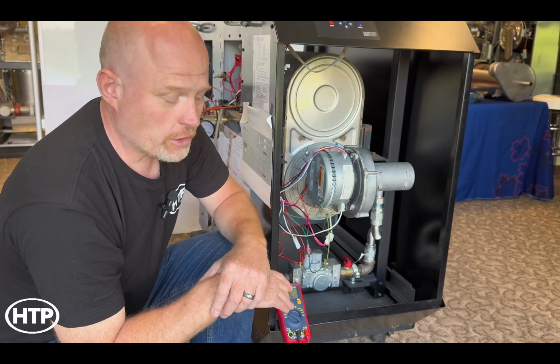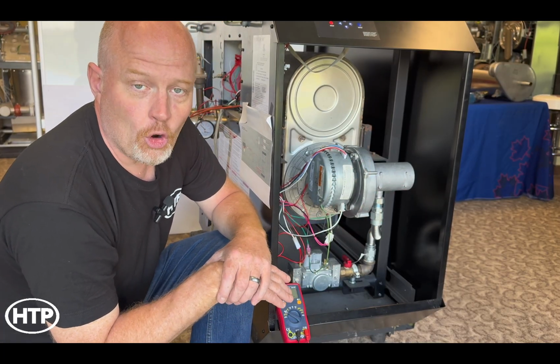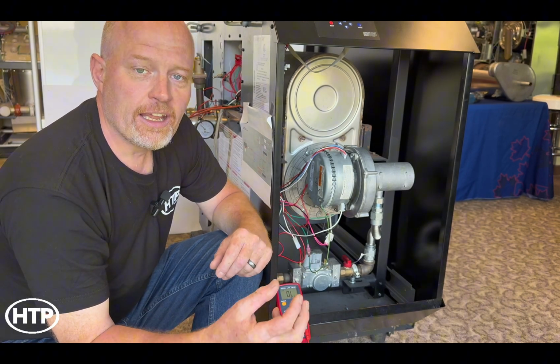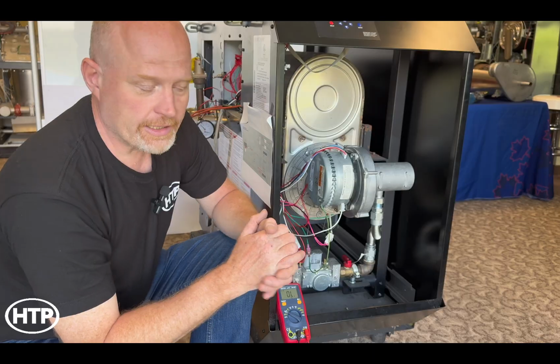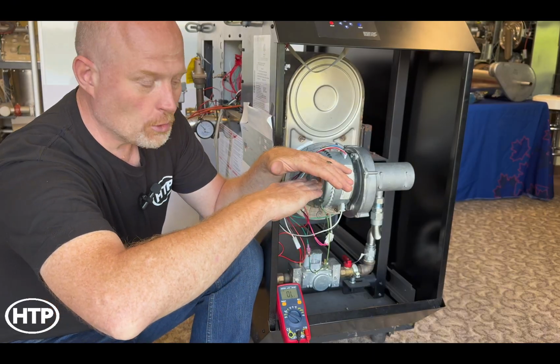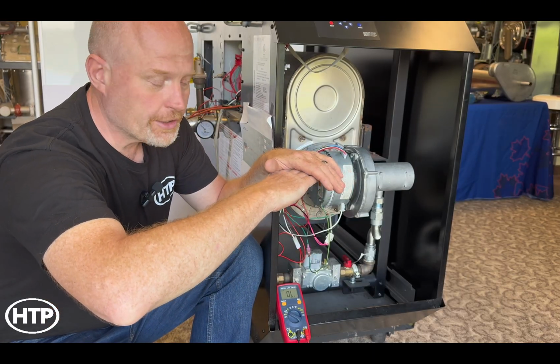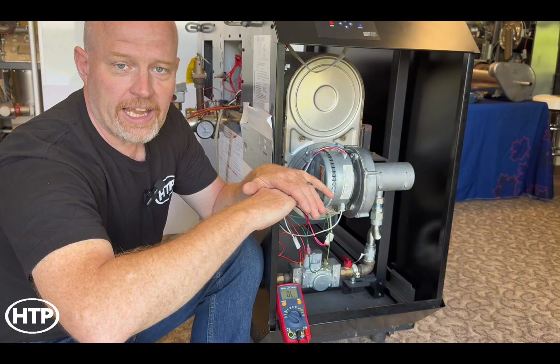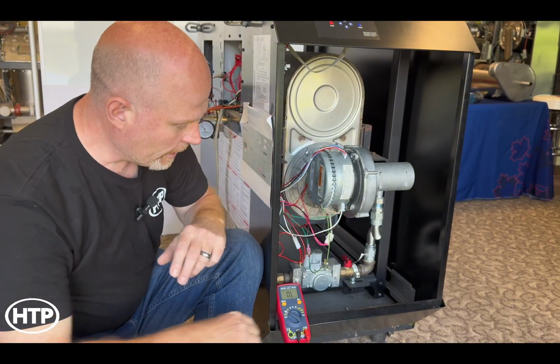Now the controller is looking for that to start in the open position. So electrically the switch will be open, then it's going to start the fan. You should hear a bit of a click or a clunk. There's a little magnet in there that helps to hold the flapper up in place once it's triggered. And at that point it should remain closed until your burner shuts off and the fan stops completely.